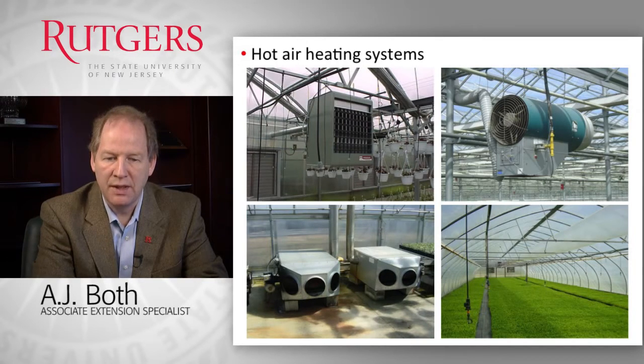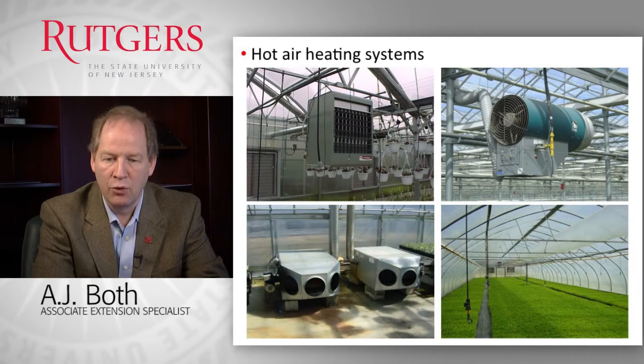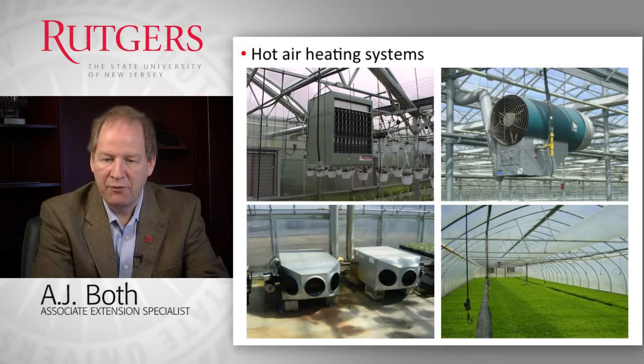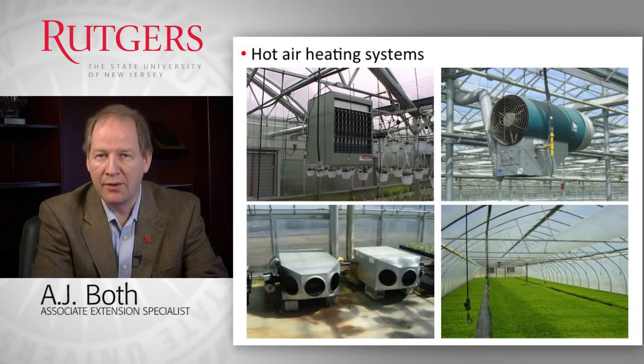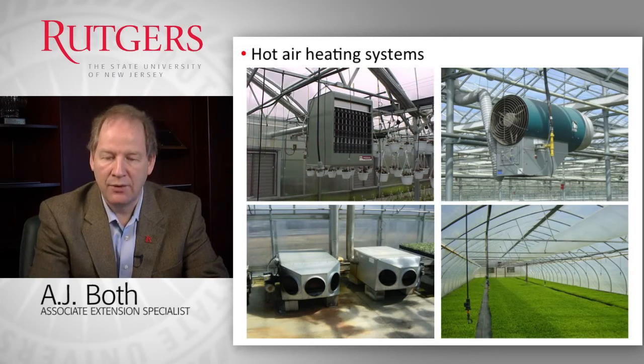As you can see in the pictures showing actual heating systems, when we have hot air systems we have strong jets of warm air located from fixed positions in the greenhouse, and that creates issues with distributing air more uniformly. On the lower right-hand image you can see a polytube running overhead, inflated by the fan attached to the unit heater, and warm air escapes through little openings along the entire length of the tube to more uniformly distribute heat throughout the greenhouse environment.